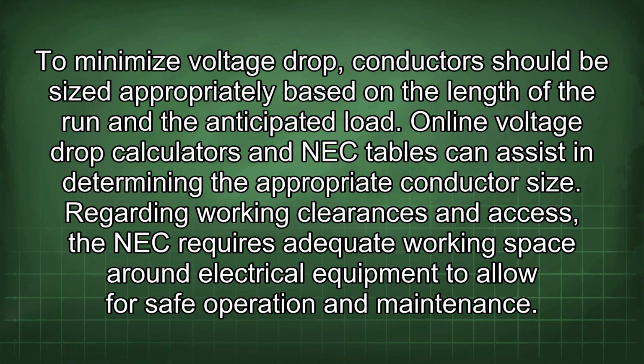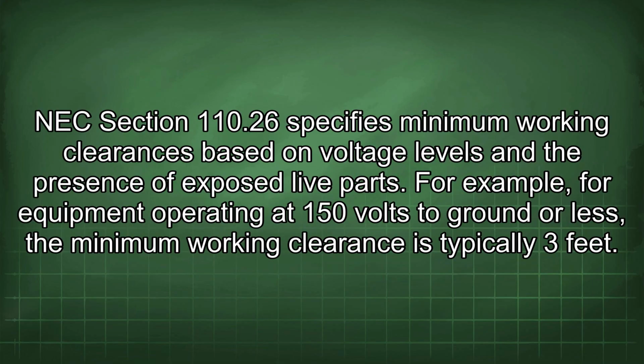To minimize voltage drop, conductors should be sized appropriately based on the length of the run and the anticipated load. Online voltage drop calculators and NEC tables can assist in determining the appropriate conductor size. Regarding working clearances and access, the NEC requires adequate working space around electrical equipment to allow for safe operation and maintenance. NEC Section 110.26 specifies minimum working clearances based on voltage levels and the presence of exposed live parts.